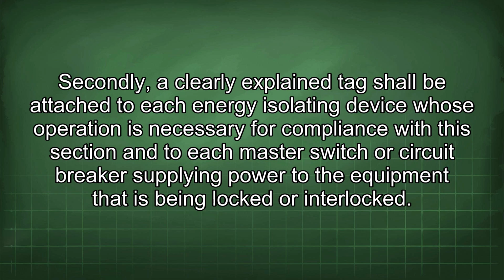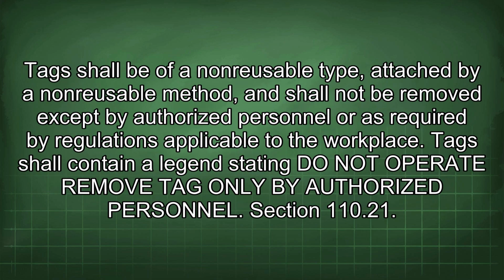Secondly, a clearly explained tag shall be attached to each energy isolating device whose operation is necessary for compliance with this section, and to each master switch or circuit breaker supplying power to the equipment that is being locked or interlocked. Tags shall be of a non-reusable type, attached by a non-reusable method, and shall not be removed except by authorized personnel or as required by regulations applicable to the workplace. Tags shall contain a legend stating "Do not operate, remove tag only by authorized personnel."